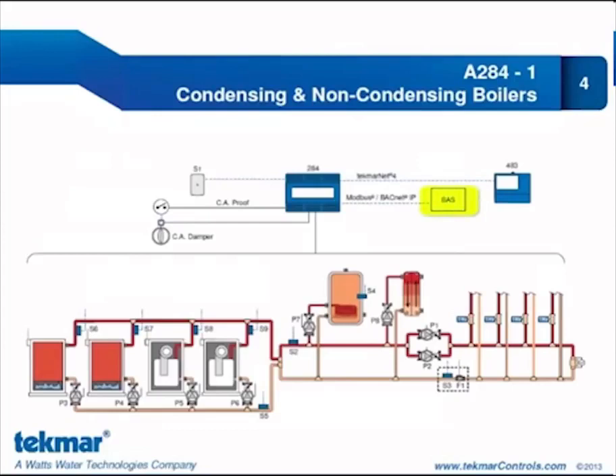We have attached the 284 to a building automation system, communicating with either Modbus or BACnet IP — it's one or the other, we can't do both. We are also connected to a gateway 483, communicating certain information using the tekmarNet4 communication. We have connected an outdoor sensor to provide a reset water temperature for the space heating zones. We're also controlling a combustion air damper, using its end switch to provide combustion air proof to the 284. This is optional — we can control the combustion air damper without proof, but if configured for proof, we will not operate the heating plant until proof is received.